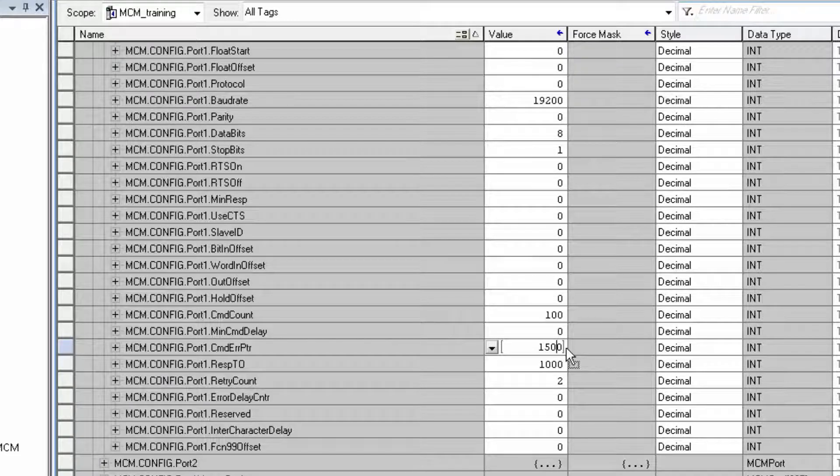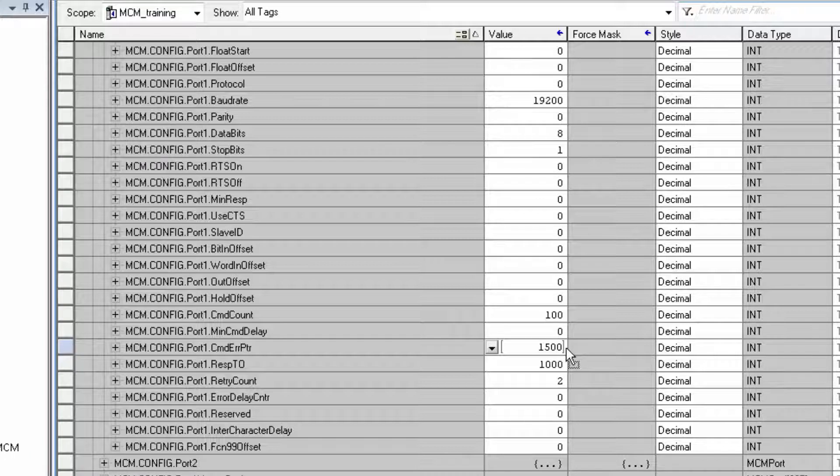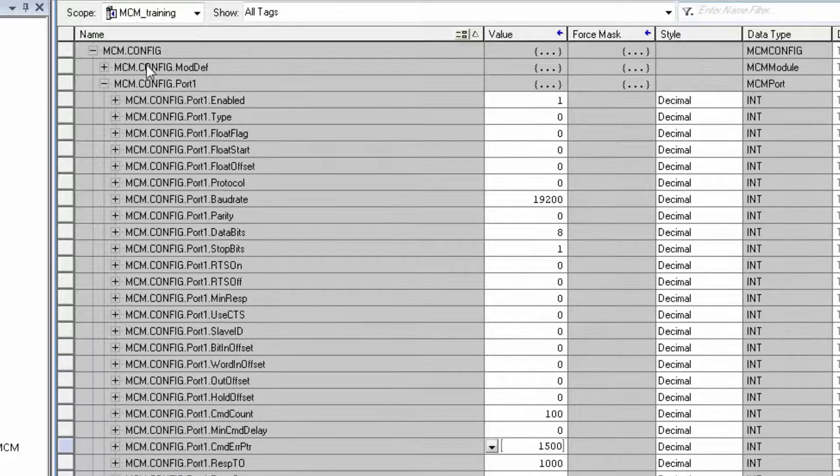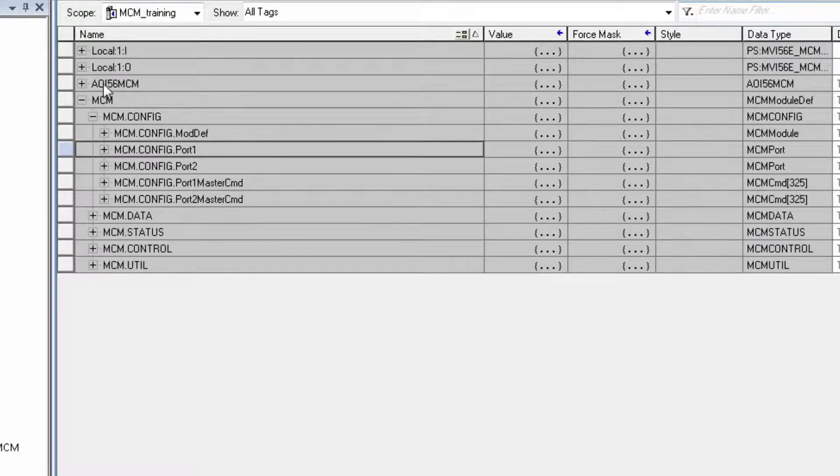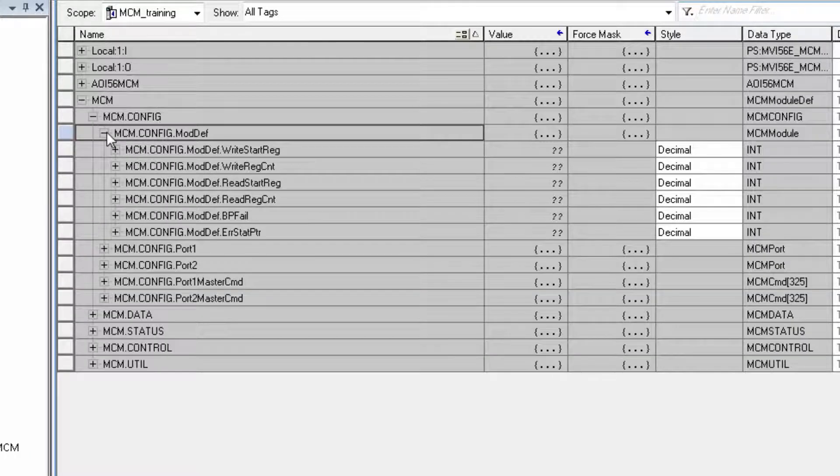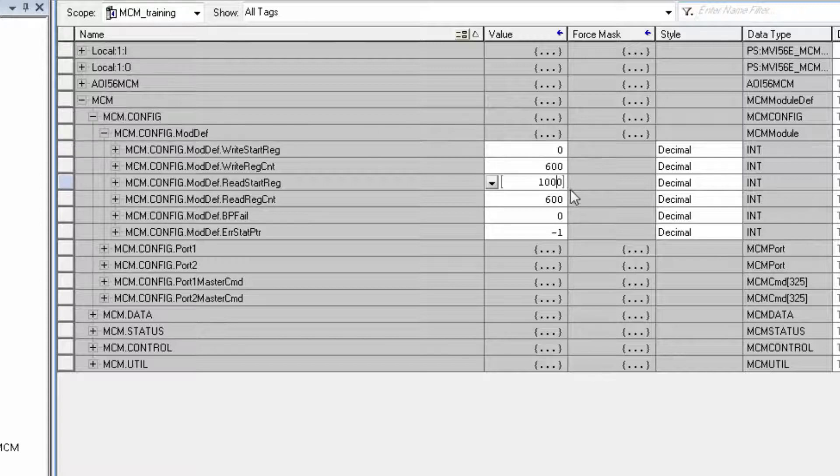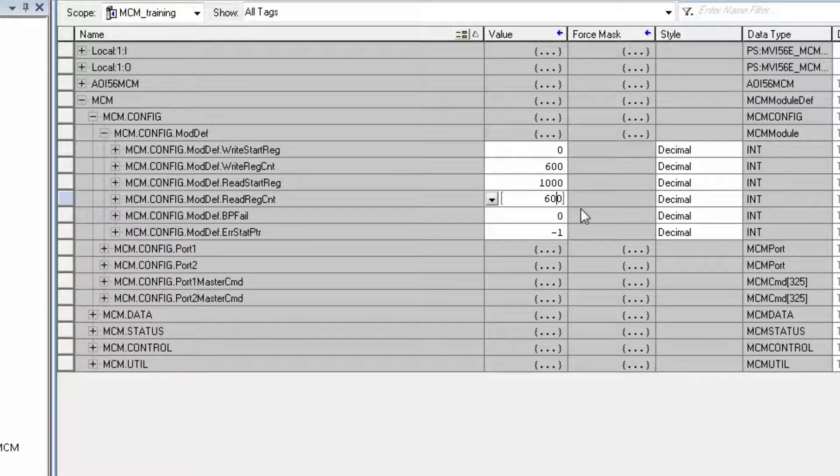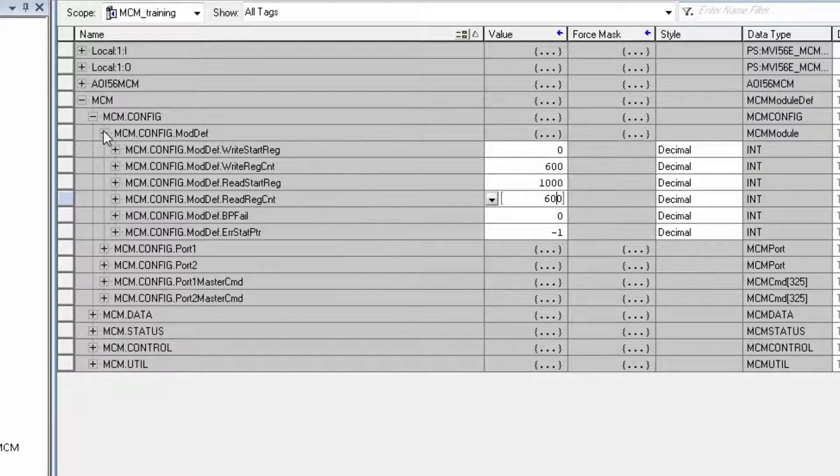And again, to be useful in the application, the error codes must be placed within the MCM.data.readData array. For the MCM, the read data starts at internal address 1000 with a register count of 600. That's default. We'll place the error pointer to begin towards the end of our read data.